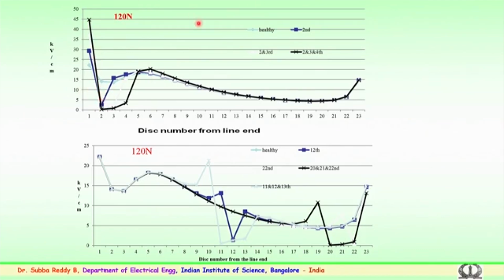In this case, the potential gets entirely modified and you can see the rise in potential near the first disc. Once this rise in potential happens, you can see somewhere from here to here the stress at the line end increases, and there could be discharges across the first disc insulator. Initially, the cascading effect could cause a serious blow to the string. So, immediate replacement is required.